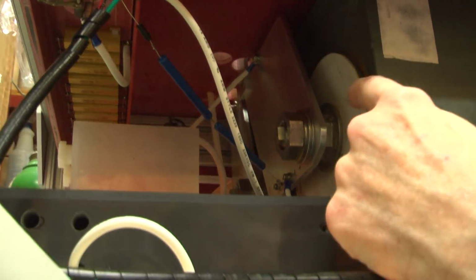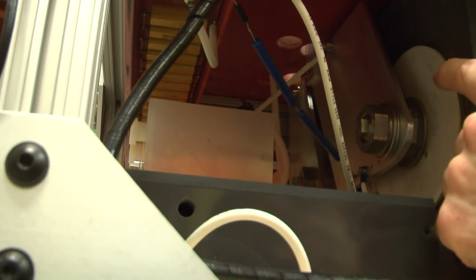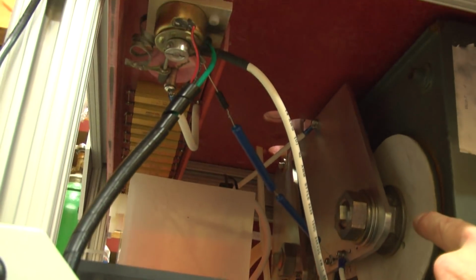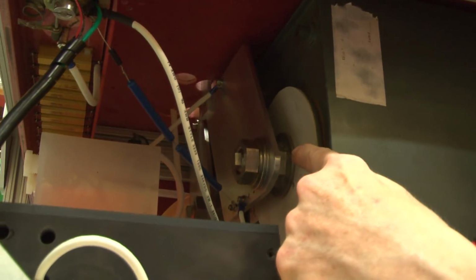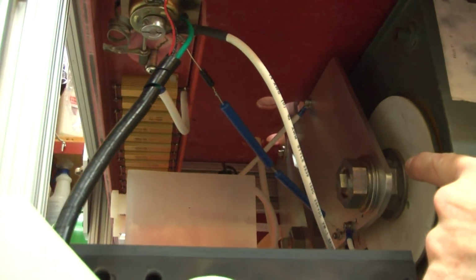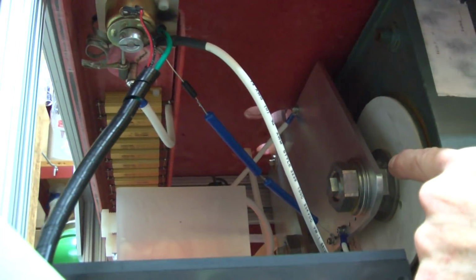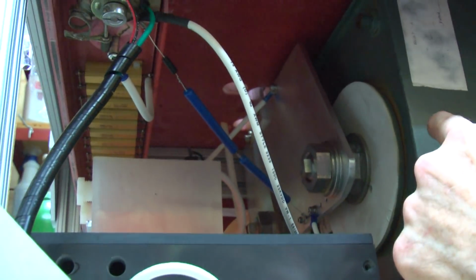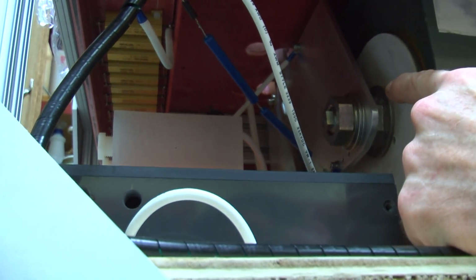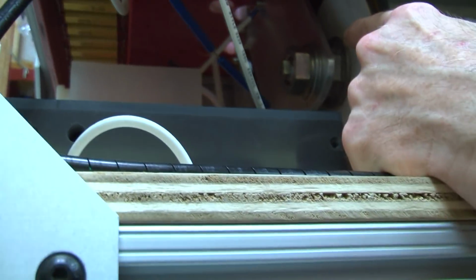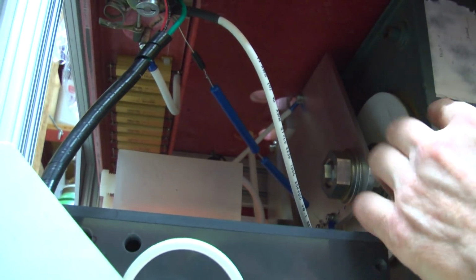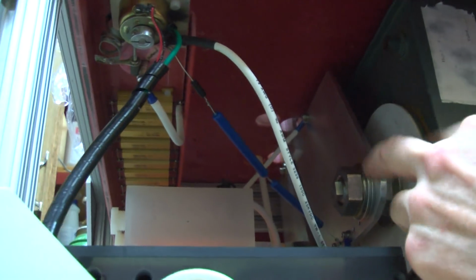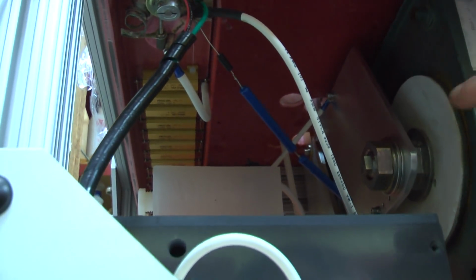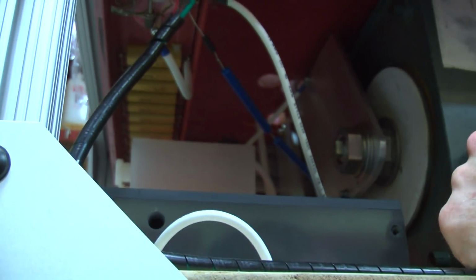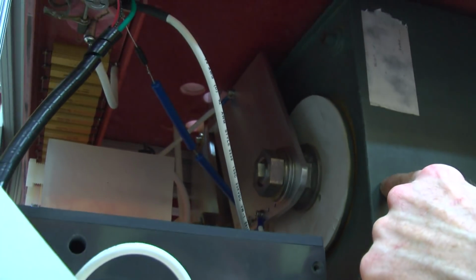This capacitor is so far beyond lethal that touching the high voltage post wouldn't just electrocute you, it would blow your hand clear off — there's that much energy in there. So crowbarring is just not possible. It's also very damaging to the capacitor, because it produces a very high mechanical loading that rings back and forth between the two posts — the voltage inverts and rings down over 10 or 20 cycles, damaging the capacitor very quickly.